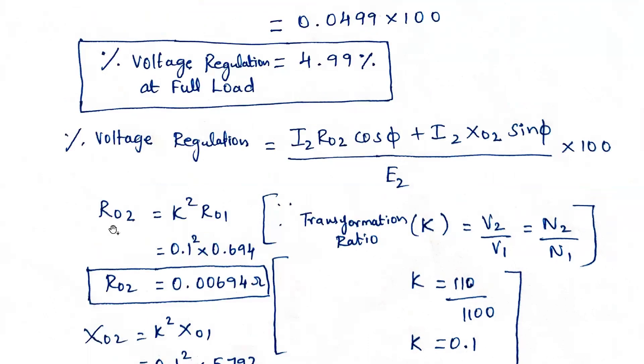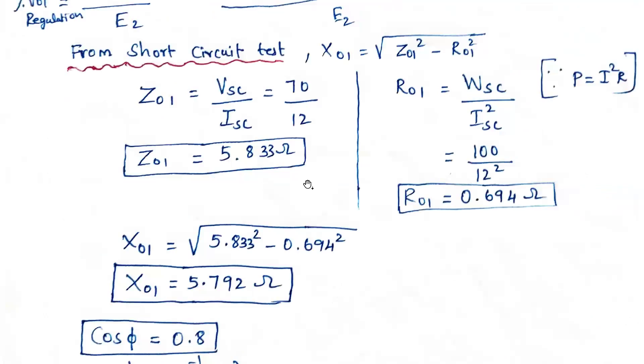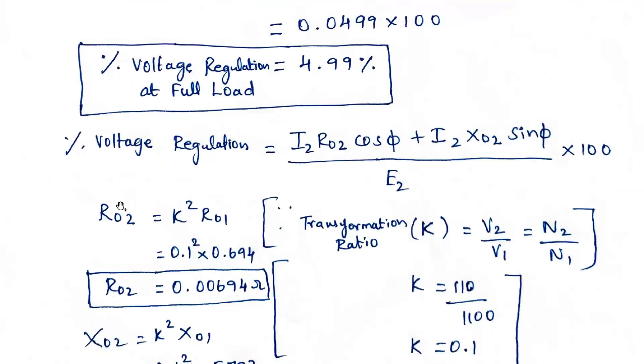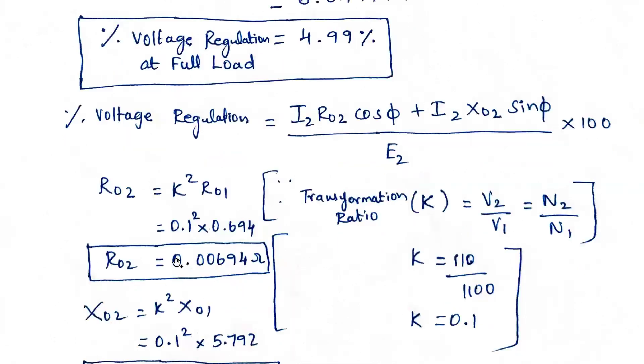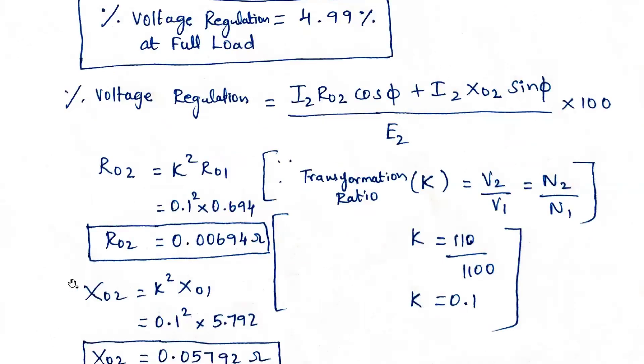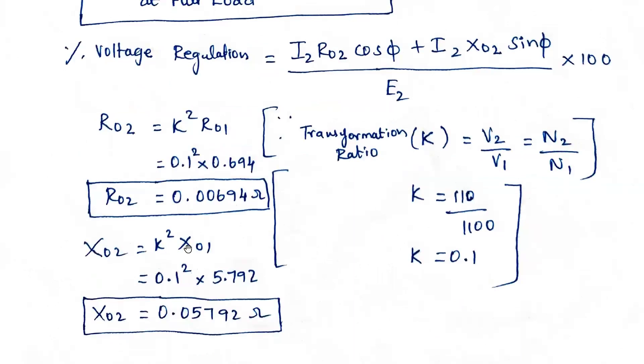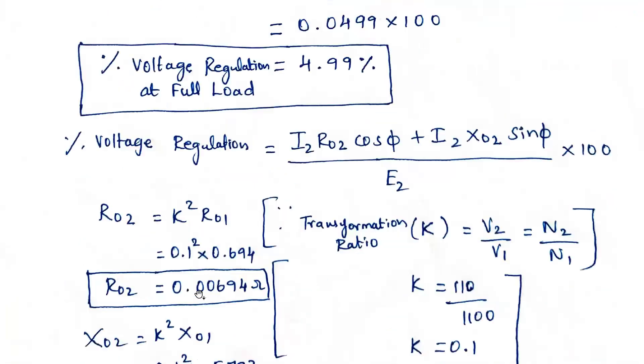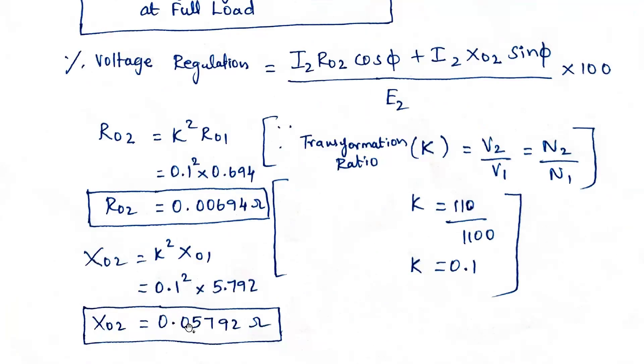To convert primary values to secondary, we multiply by k². R₀₂ equals k² × R₀₁ = 0.1² × 0.694 = 0.00694 ohms. Similarly, X₀₂ equals k² × X₀₁ = 0.1² × 5.792 = 0.05792 ohms.